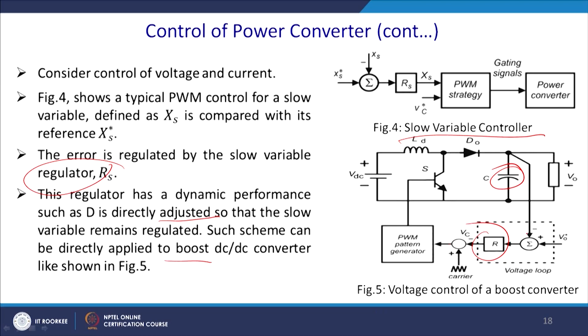Now, this figure 4 shows the typical PWM control of the slow variable defined as Xs compared with its reference Xs prime. Here it is nothing but the DC bus voltage and the reference DC bus voltage. The error is regulated by the slow variable regulator Rs, that may be a PI controller. The regulator has a dynamic performance such that D is directly adjusted, so that the slow variable remains regulated. Such a scheme can be directly applied to, for example, a boost converter, or any other converter, as shown in figure 5. So, this is called voltage mode control of a DC to DC converter.